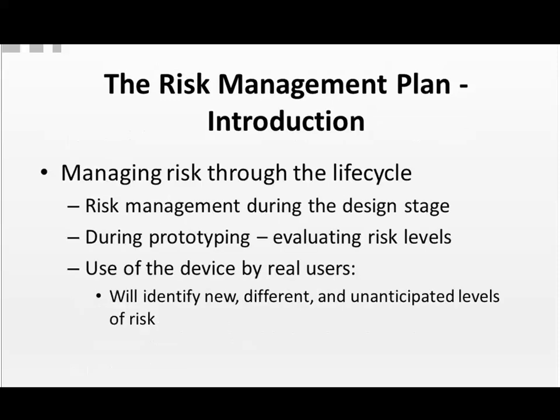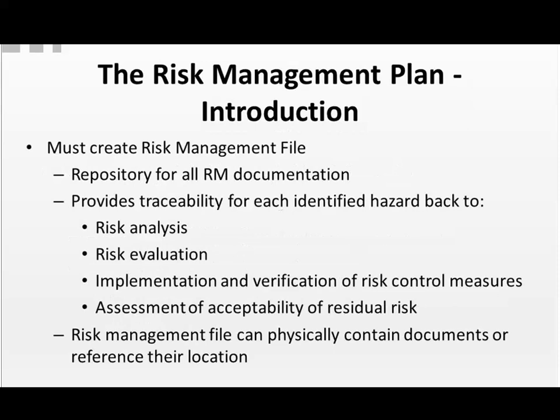Now, as I've said, risk is managed throughout the entire life cycle of the device. Initially, during the design process, that evaluation is essentially a rough estimation of the risk. As feedback from real users is gathered during the device's life, new and different and certainly unanticipated levels of risk will be exposed. Now, we briefly mentioned the risk management file, but to provide some additional detail, you see here that it's a repository for all the risk management documentation that we've identified.